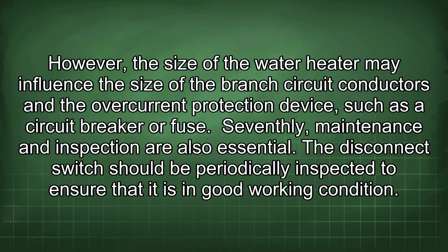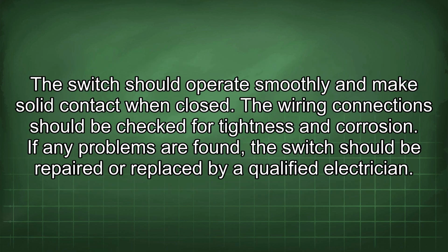Seventhly, maintenance and inspection are also essential. The disconnect switch should be periodically inspected to ensure that it is in good working condition. The switch should operate smoothly and make solid contact when closed. The wiring connection should be checked for tightness and corrosion. If any problems are found, the switch should be repaired or replaced by a qualified electrician.